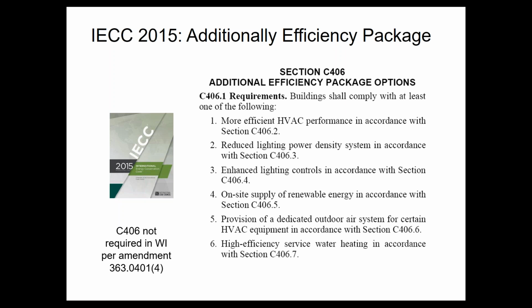Pick one of these 6 things. In 2012, there were 3 on the list. Now there's 6 things to pick from. You can either make your HVAC equipment more efficient. You can make your lighting power density lower. You can add lighting controls. You can add renewable energy, right? You can do something with the service water heating. Got some choices here. For you guys that do HVAC, if it's a chiller system and a boiler system, you could probably do item number 1 fairly easily and comply that way. If it's a rooftop project, you need to get the designer of the building, the architect, to completely avoid option number 1.